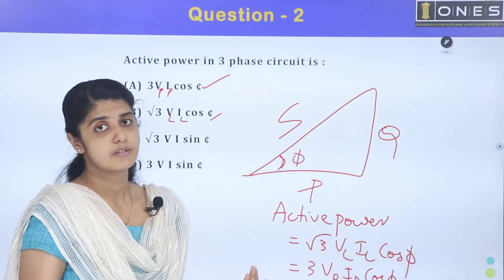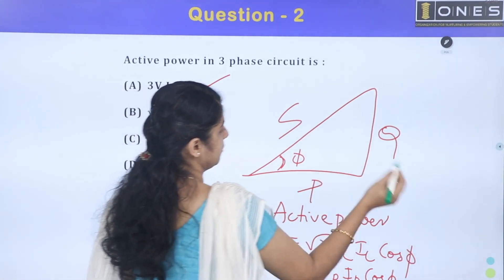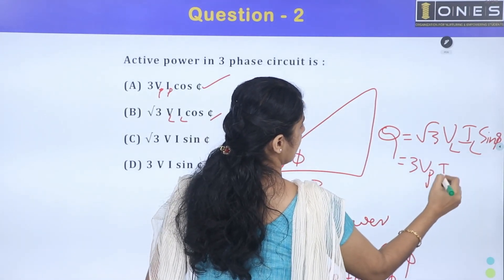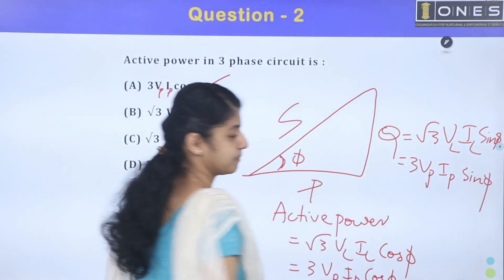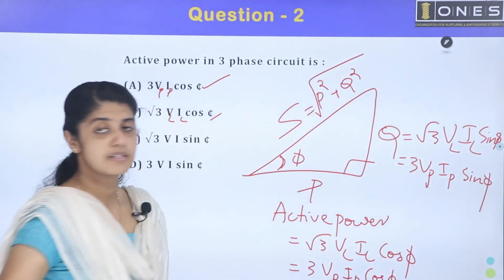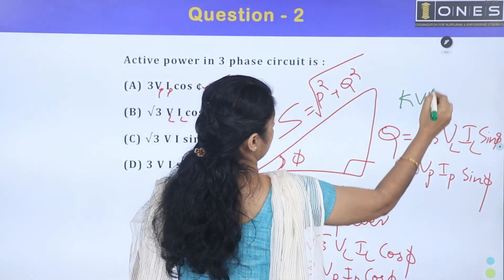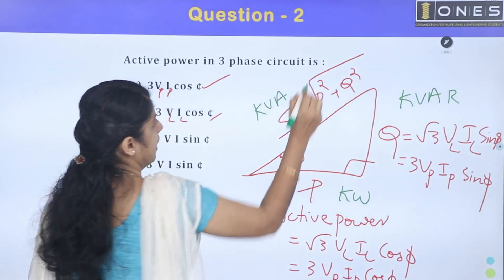Active power is root 3 VL IL cos φ, which equals 3 VP IP cos φ — the phase value equals line value. Reactive power Q is root 3 VL IL sin φ, equal to 3 VP IP sin φ. Apparent power S equals the square root of P squared plus Q squared. Units: active power is kW, reactive power is kVAR, and apparent power is kVA.